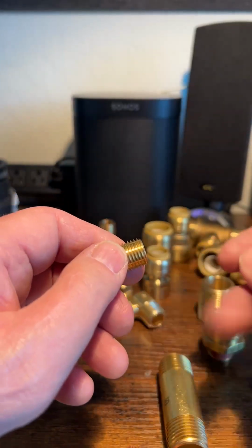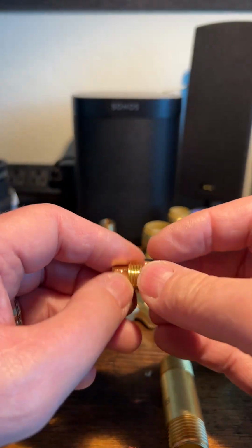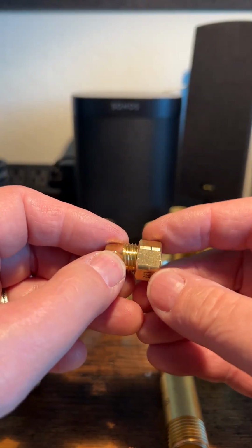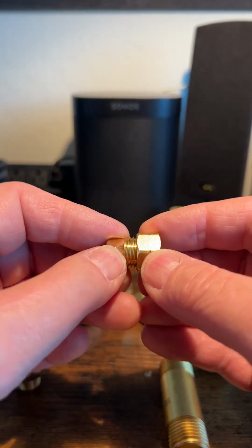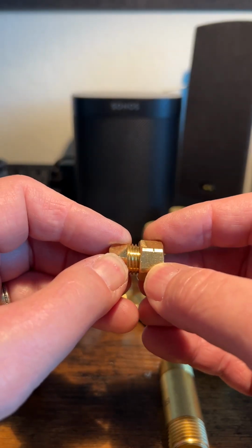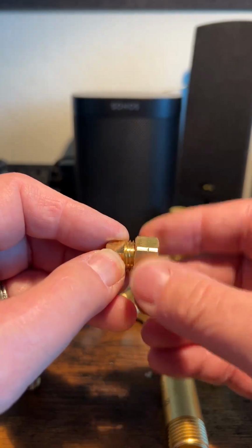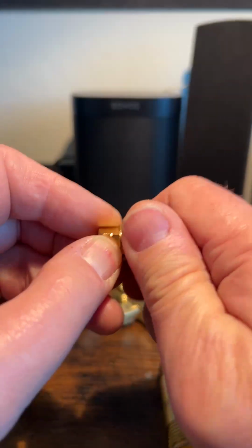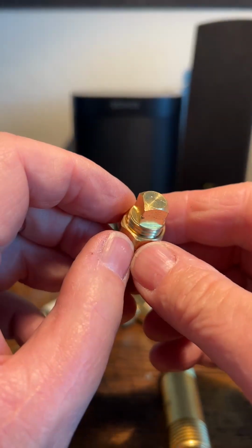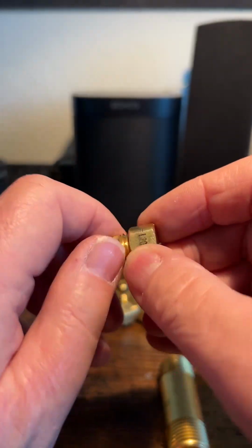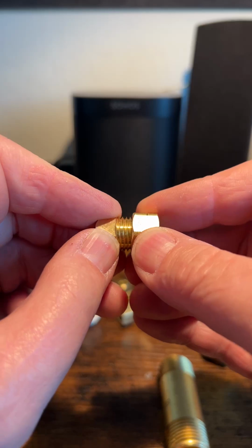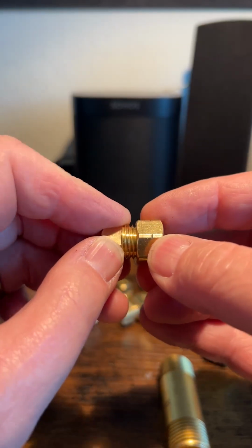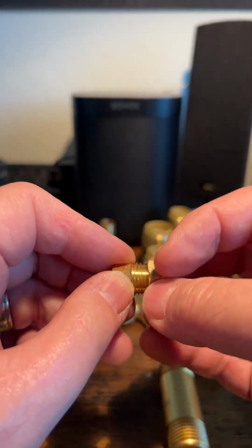Will it screw on there? It will. But you'll know if you got it wrong or not by when you first start it. It looks like it's going on there fine. But you see all that slop it has? It's going to have slop all the way down until it tightens up. And it'll tighten up, but I guarantee you this will leak out past these threads because they're not exactly the same. They might work, but if you see a lot of slop going in, it is not going to be correct. All right?